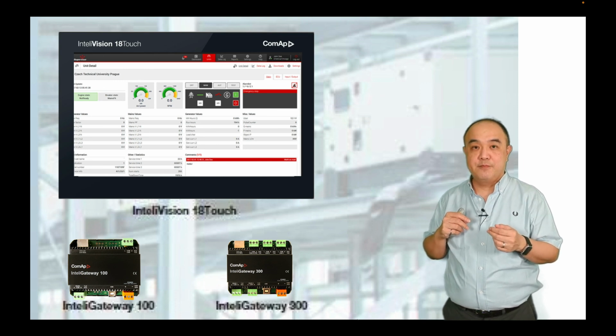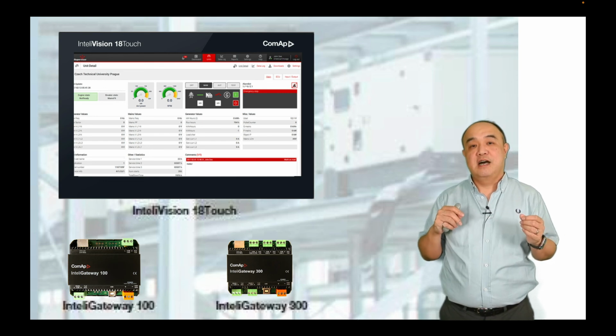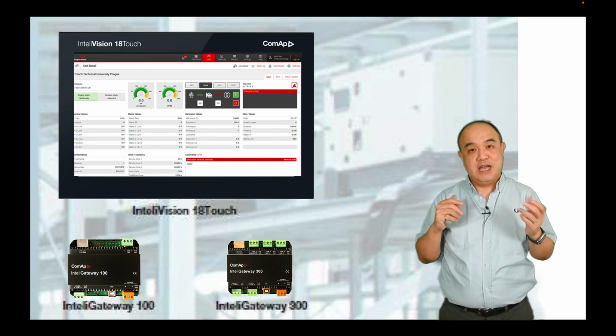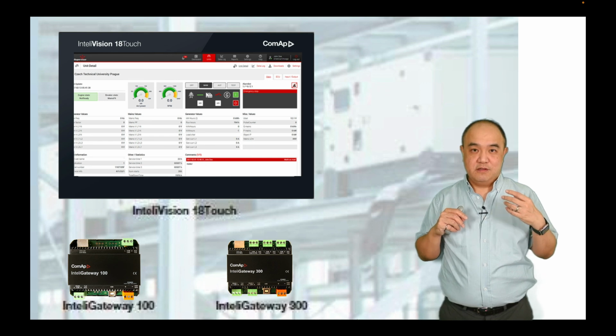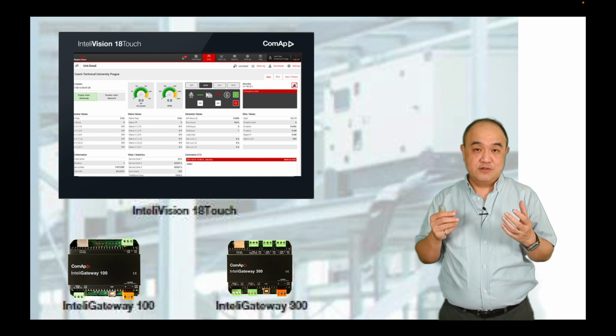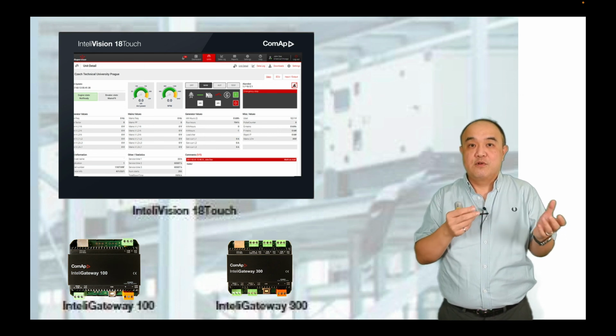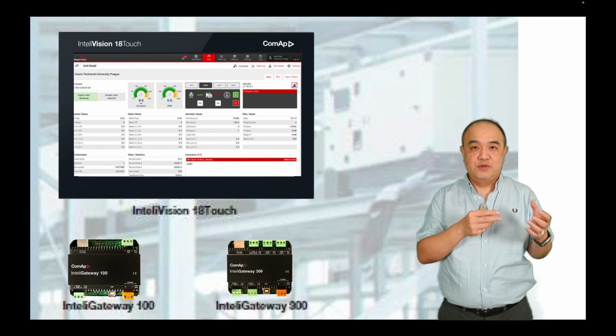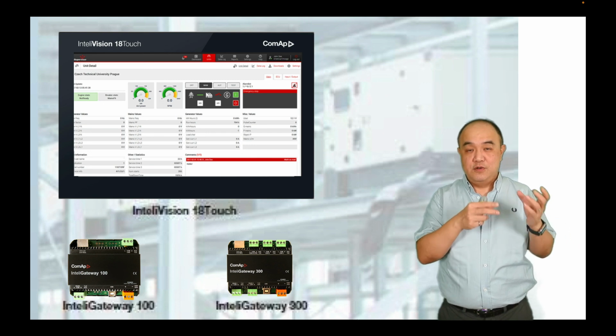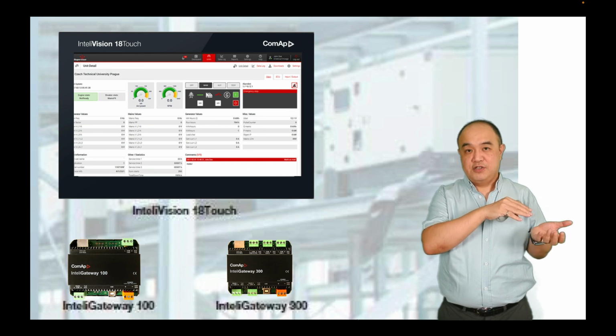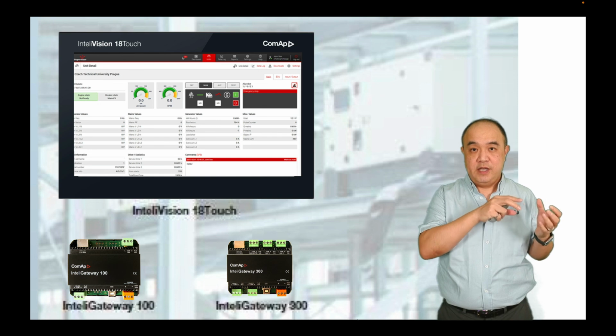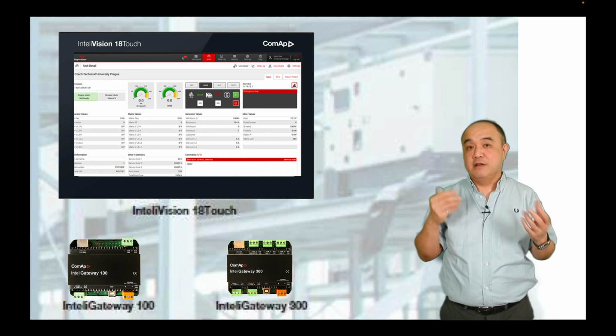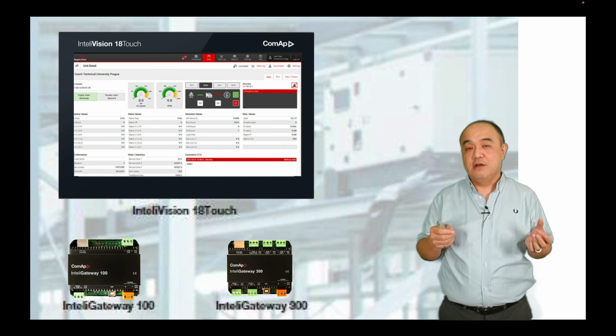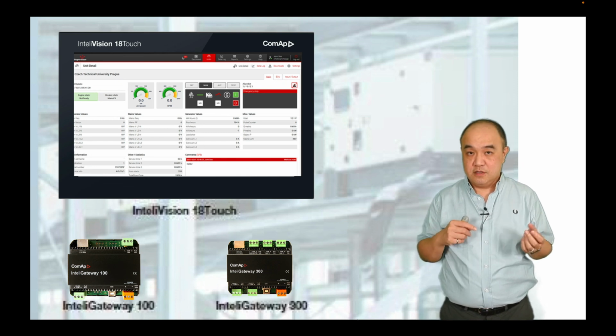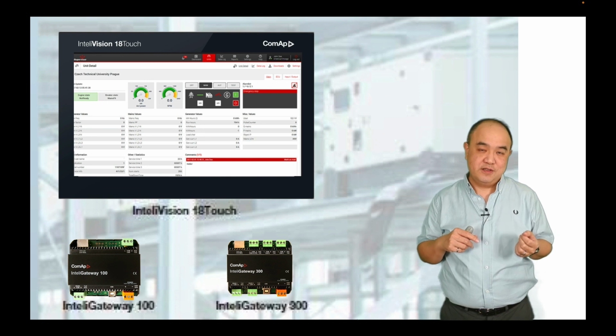Below you will see two InteliGateways - these are new products. ComAp will release them very soon, but we already have them on show. One of the gateways is for connecting to third-party controllers or devices. Say you have an inverter running Modbus TCP or Modbus RTU and you want to see how it's performing - you can use InteliGateway 100 to read the Modbus RTU or Modbus TCP, and it can then go on to ComAp's WebSupervisor so you can monitor your inverter there. So not only can you use ComAp's own controllers, you can also use third-party controllers and devices, as long as they have Modbus TCP or Modbus RTU - we can monitor it and put it in the WebSupervisor.